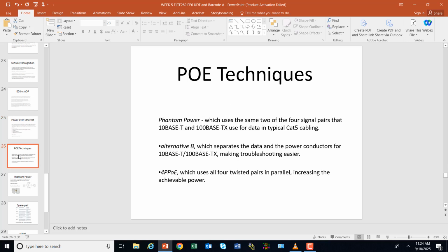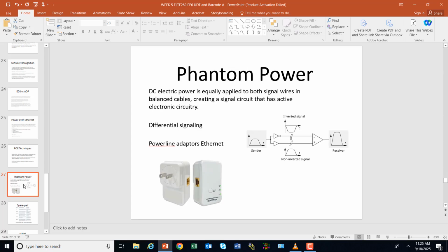So with your power over Ethernet techniques, you'll see things like phantom power, which uses the same two of the four signal pairs, and there's alternate B, which separates the data and power conductors. And then there's 4PPoE, which uses all 4 twisted pairs in parallel, increasing achievable power. So depending on how much power over Ethernet you want, these are some of the things you have to talk about.